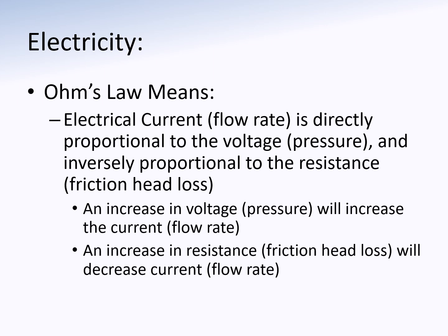Recently, on one of the engineering projects at VID, there was an issue where they wanted to put in a larger pump than the power that was available at that site, and unfortunately, the engineer who was doing that design missed that detail. He just assumed that there was enough power there to operate this pump, and yeah, that led to some discussions. So that's why we want to know these things.